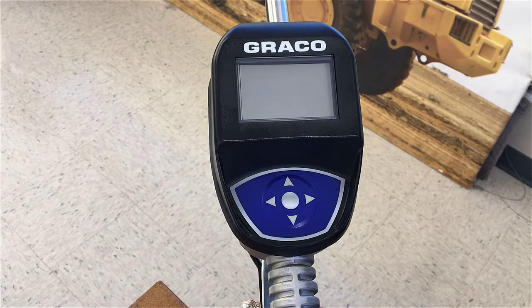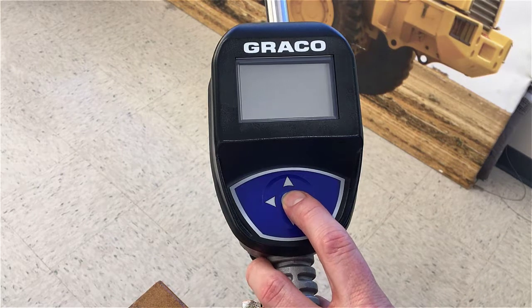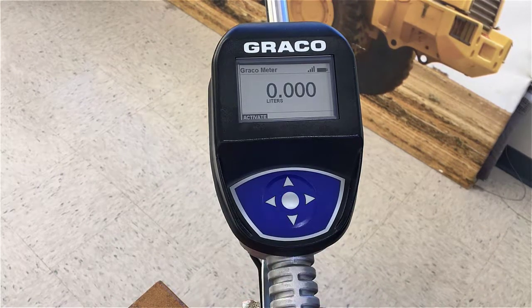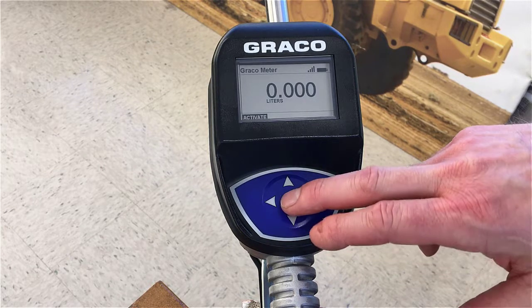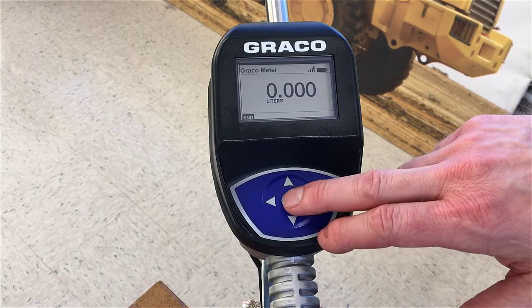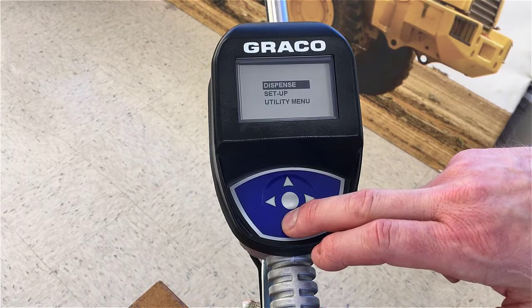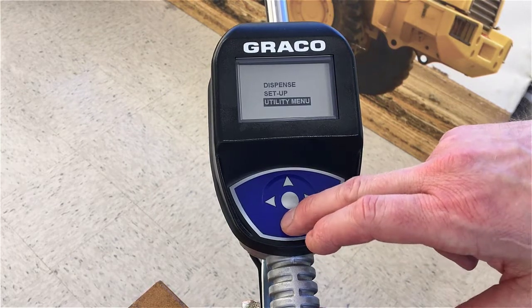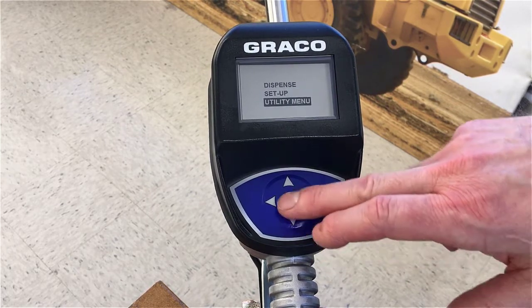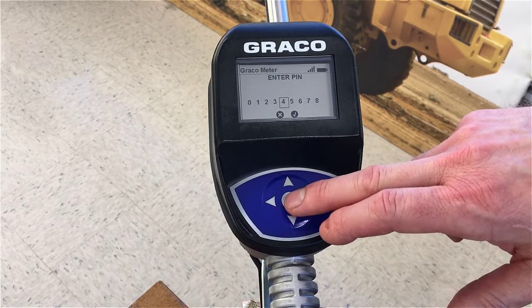To calibrate a pulse meter, first you have to wake up the meter, so press any button on the keypad to wake it up. It first takes you to the dispense screen. In dispense mode, press the center button to activate — you'll hear the solenoid click — and then press the center button again to end. The solenoid clicks again and now we are in the dispense, setup and utility menu screen. Choose utility menu and put in the PIN code to access the utility menu.